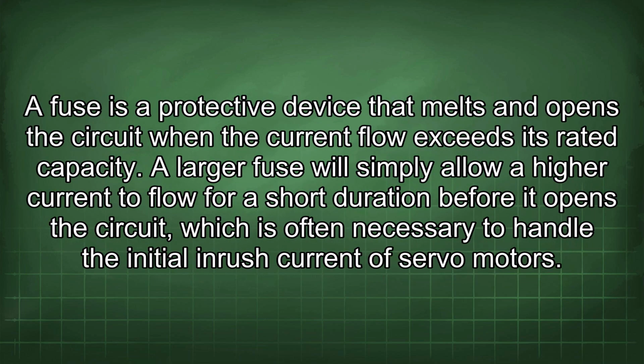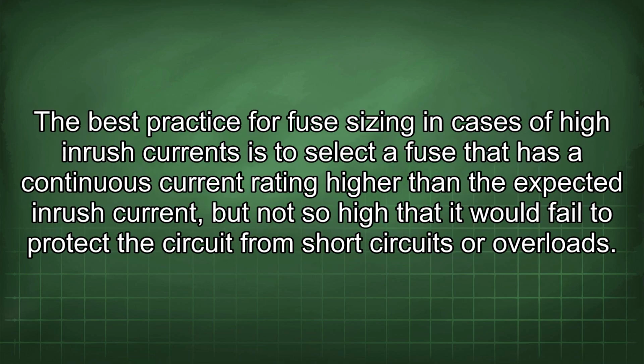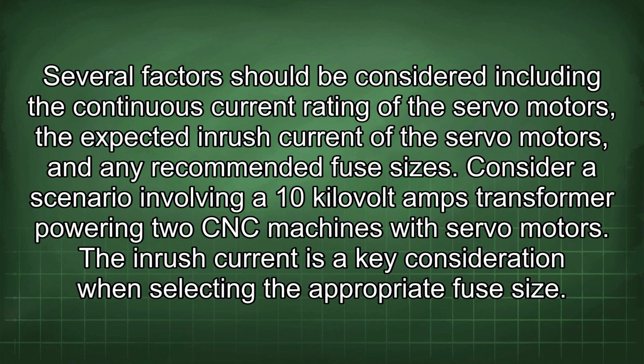A fuse is a protective device that melts and opens the circuit when the current flow exceeds its rated capacity. A larger fuse will simply allow a high current to flow for a short duration before it opens the circuit, which is often necessary to handle the initial inrush current of servo motors. The best practice for fuse sizing in cases of high inrush currents is to select a fuse that has a continuous current rating higher than the expected inrush current, but not so high that it would fail to protect the circuit from short circuits or overloads. Several factors should be considered, including the continuous current rating of the servo motors, the expected inrush current of the servo motors, and any recommended fuse sizes.